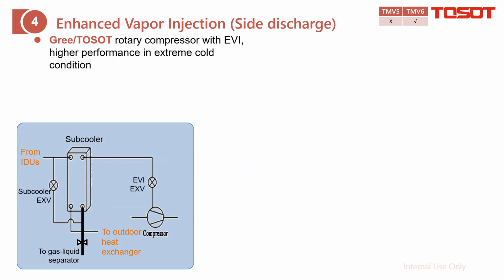Enhanced vapor injection for side discharge. First of all, let's focus on this diagram. You can find that here is a subcooler. It is actually a plate heat exchanger. This one is from the indoor unit, and here to the compressor, and also here is a subcooler EXV, and this is to the outdoor heat exchanger.